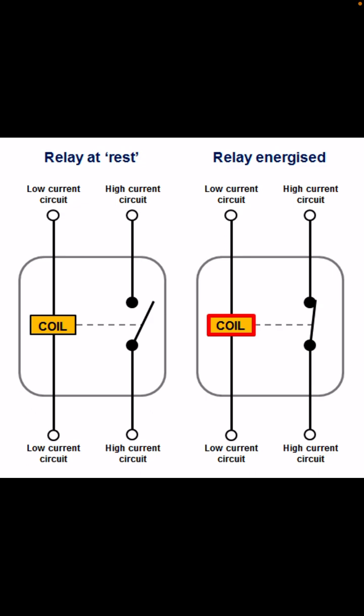It'll open back up. Say like a time delay relay for HVAC. It's going to be closed normally, letting voltage through, but after a certain time is met, it's going to open those contacts and stop letting voltage go through. So that would be the difference between a normally open and a normally closed. Usually you'll be able to see either on the wiring diagram, or on the actual relay itself, it'll have like little schematics, and different symbols will mean different things. But we'll go more into that on a different video on how to read schematics and wiring diagrams.